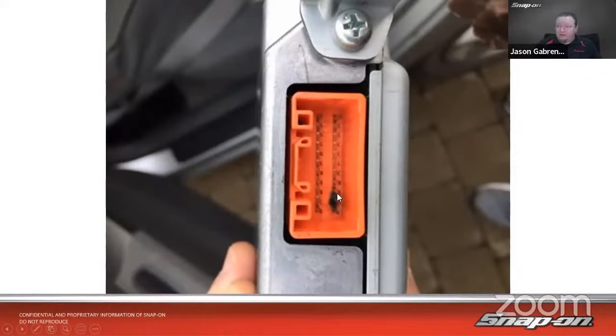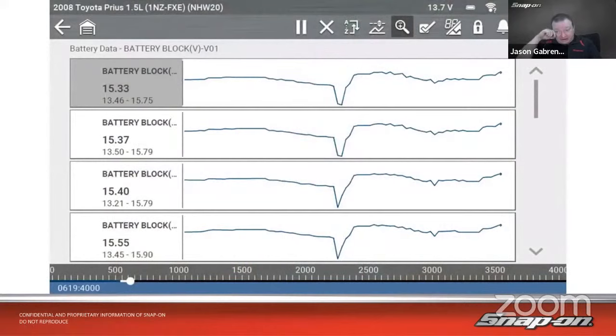You can see we got some green fuzzy stuff in there, and it's all corroded as well. So that was a problem, and they had to end up replacing this whole module because of that. They cleaned the battery contacts internally, replaced the module, got that all done, and then decided to double check their work. The fault was cleared and went away.